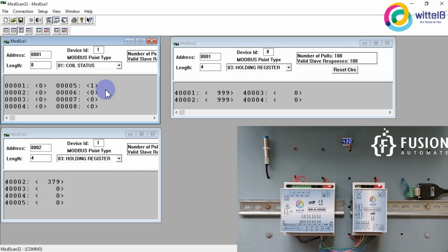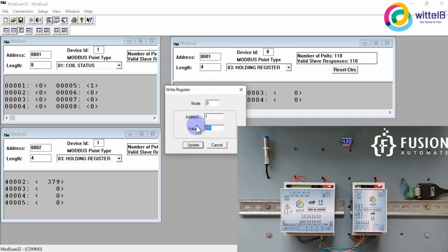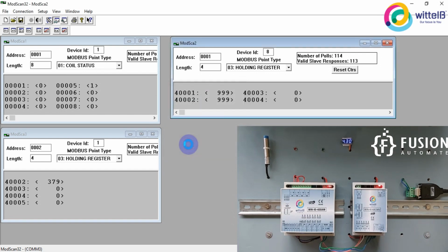Now the analog output card. You already know that the analog output card has a slave ID of 8. I have set this analog output card to 10 bit, so the maximum value I can provide is 1023. I have already provided 999. If I provide a 0 value here, then this DC voltmeter will be turned off. So let me update it. You can see my DC voltmeter got turned off and I am having 0 here.